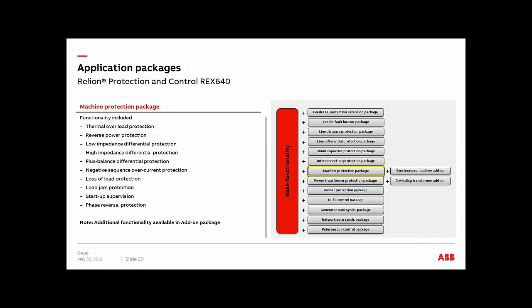Moving on to the machine protection package, we got the 49M, the thermal overload protection. You also get a reverse power protection. In this case, you do have a low impedance differential protection that will give you your stabilized protection with settable slopes, as well as a high stage unrestricted instantaneous differential trip. There's also the option of having a high impedance differential protection, where you have to sum your CTs externally with your respective resistors. And there's also a flux balance differential protection. That's another option of connecting. So you do have pretty much all of the options that you could have for a machine differential when it comes to this specific package.